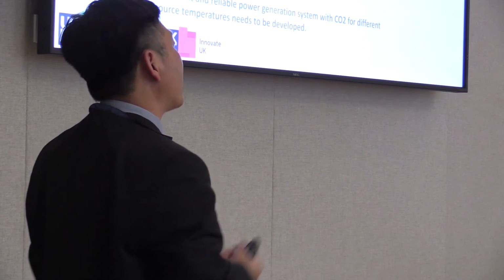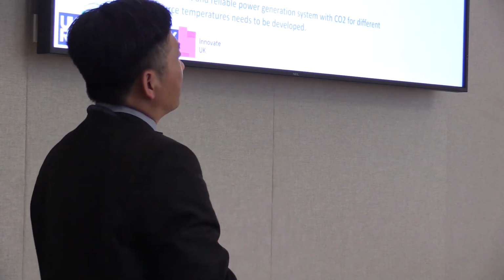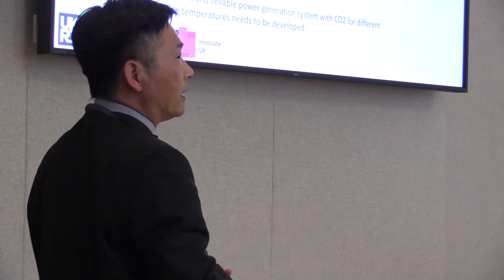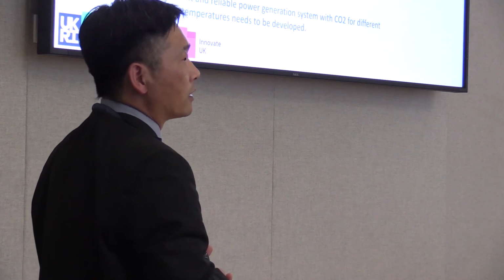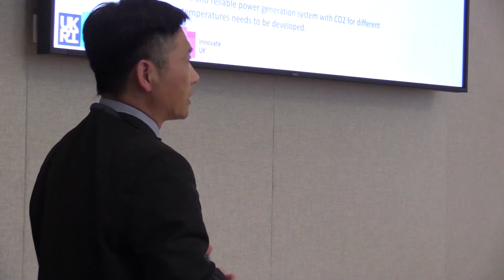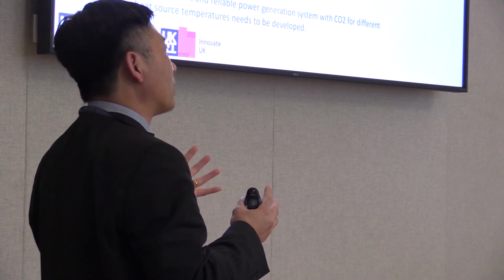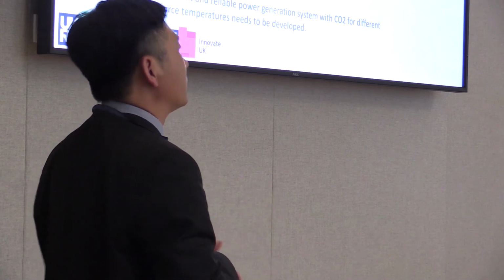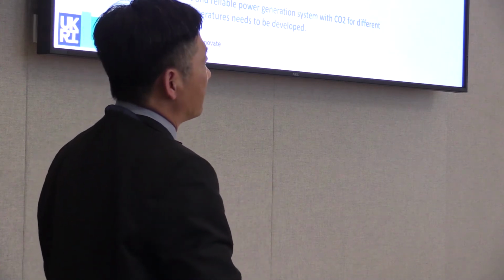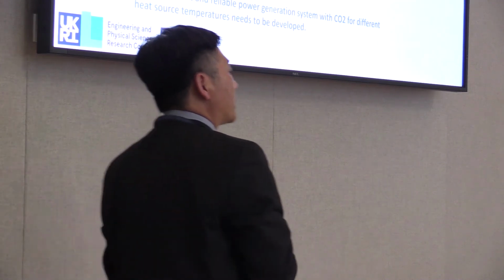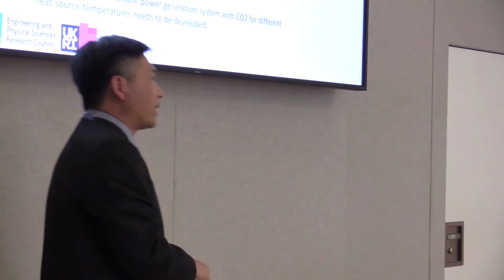So theoretically we can have a high temperature, but practically, because we are using thermal oil as a heat transfer medium, the thermal oil has a maximum usable temperature of about 350 degrees C. So you can't have a temperature higher than that. So it's difficult to practically achieve a high temperature above 300 degrees for the CO2 system.